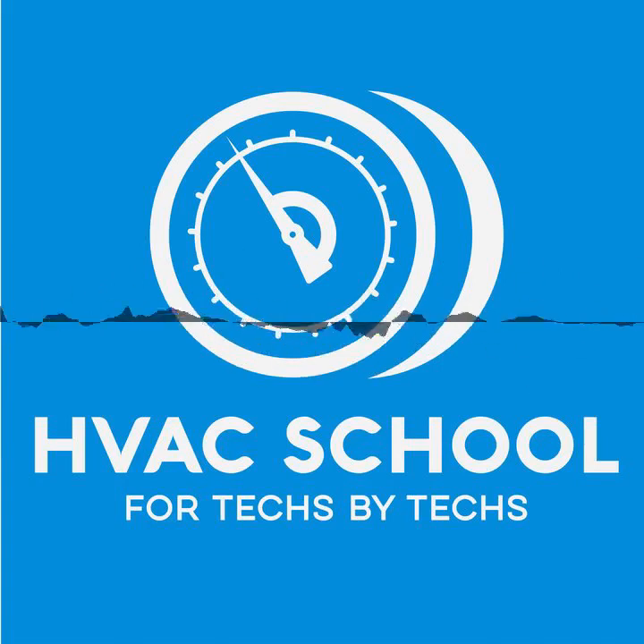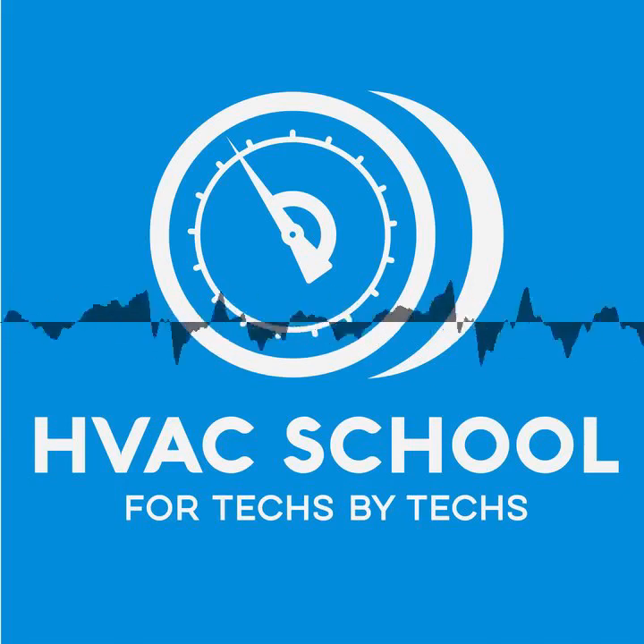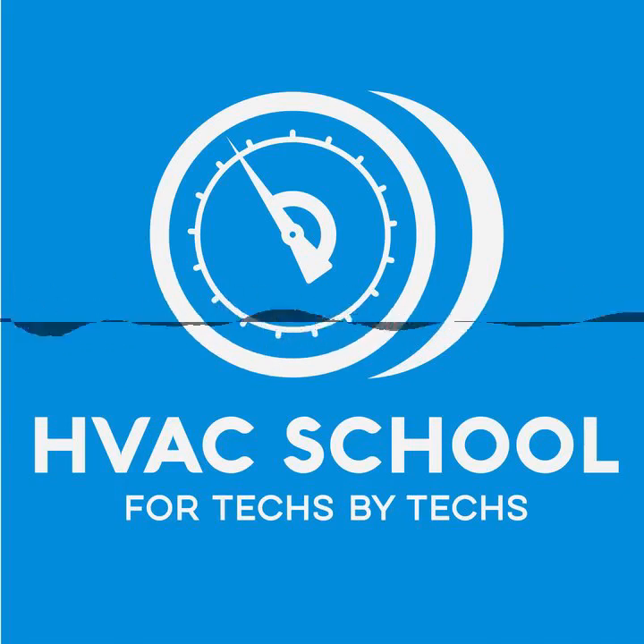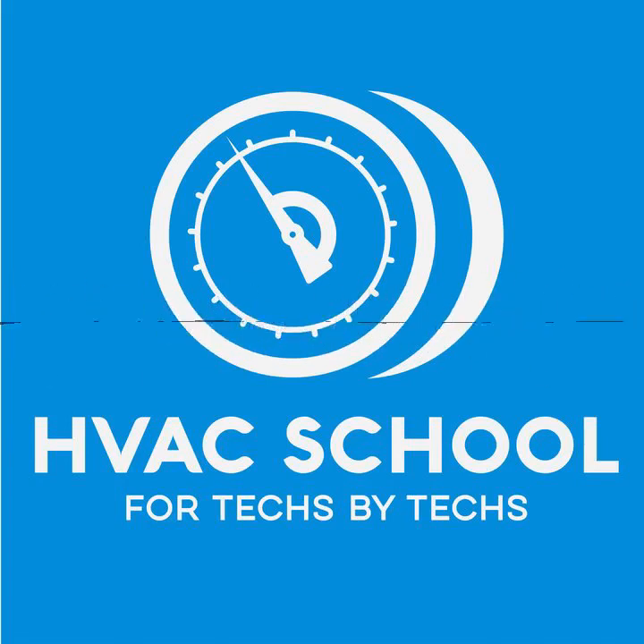I'm not going to suggest getting 3 foot hoses. I would suggest in most cases get two large diameter 6 foot hoses. Well, the only reason they're standard is because that's the length they make them. And that's no joke. Appion's probably the number one seller of vacuum rated hoses in our industry, and most of them are 6 footers by default. They can custom make you a hose any length you want, and a lot of guys will order customized lengths, but for the most part, that's why we see so many 6 foot hoses, simply because that's the way they make them.